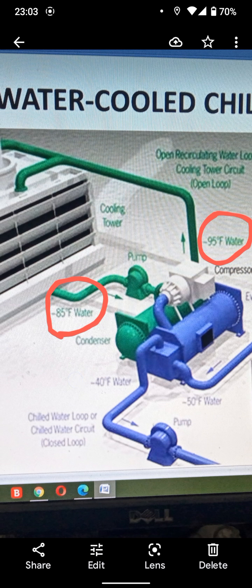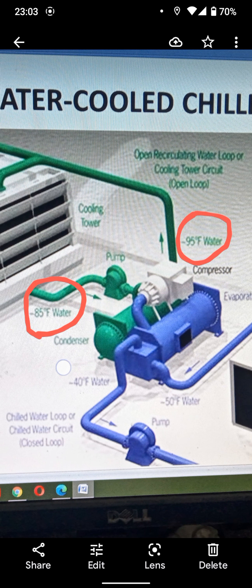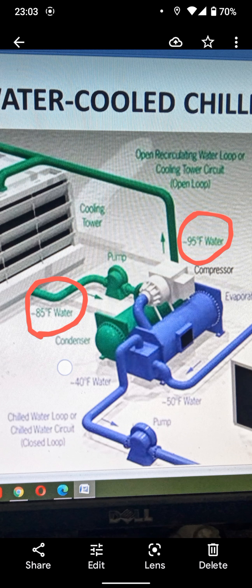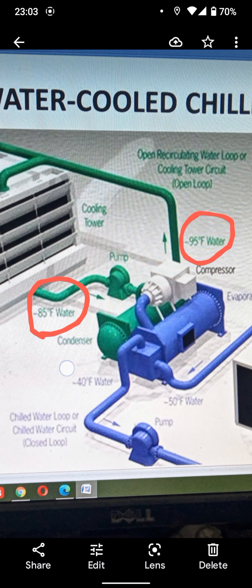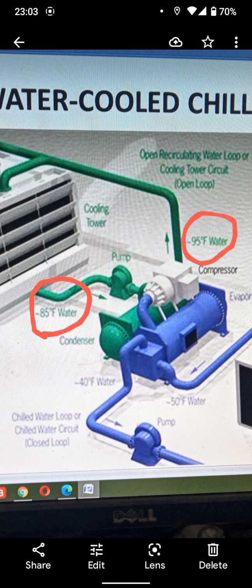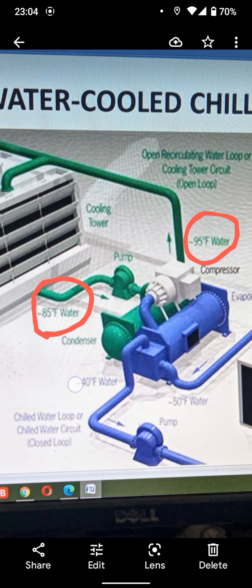Second thing we did: first we removed all 4 chiller water regulating valves. Then we started 4 pumps. Now 5 pumps are there; normally 2 run for 2 chillers, but we ran 4 pumps for 2 chillers. After running 4 pumps, what happened to the chillers? The circulation of condenser water, the cycle of the condenser water, increased to double. First we removed the auto regulating valve and opened a clear path. Second, instead of 2 pumps we started 4 pumps. So the water cycle increased in the condenser.